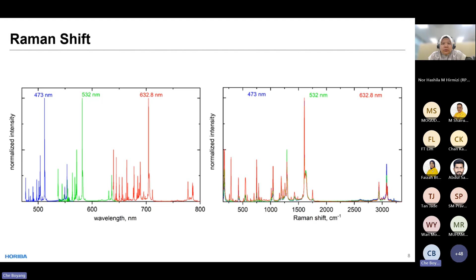So you don't really get the same pattern, and that's not good, because we use Raman as a chemical fingerprint technology, as Sheila has mentioned. We want the user to be able to identify the material no matter what light source they're using. So to achieve that, we change the x-axis from wavelength to Raman shift. After you transfer to the Raman shift, no matter whether you use a blue, green, or red laser, you always get the same pattern on the spectrum, and all the peaks are at exactly the same value. That's the difference between Raman and other types of spectroscopy technology: the X value unit is different.